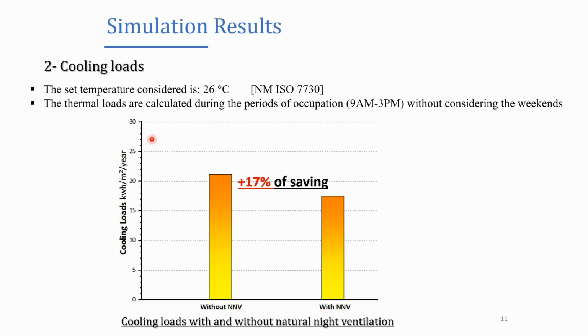The second studied parameter is the cooling load. The following figure represents the cooling load for the two studied scenarios. In order to evaluate this, the set temperature considered was 26 degrees C, and the thermal loads were calculated during the periods of occupation only, without considering the weekends. From this figure, establishing the scenario with natural night ventilation resulted in a significant reduction, 17% of saving in annual cooling loads compared with without natural night ventilation. This result promotes the efficiency of natural night ventilation in the semi-arid climate of Marrakech.